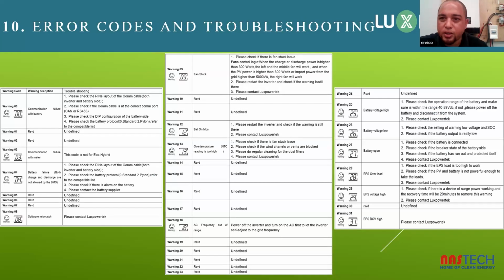There are more warning codes. Battery voltage high: ensure that the battery voltage is within the range of the inverter. Battery voltage low: obviously you need to make sure that the battery voltage is higher than 40 volts. Battery open: once your battery is open, that means the battery is much lower than 40 volts, and you need to get the battery charged up again.